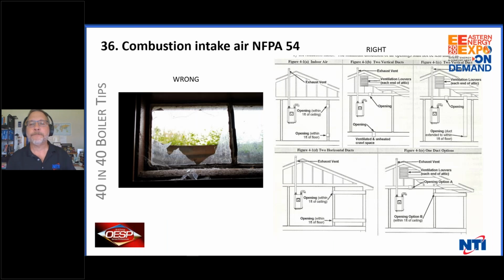Combustion air intake. From a friend of mine, Jim De Palma, who works for Weil-McLain, great guy, was nice enough to give me a visual on how much free air you need to use indoor air for combustion. He said if you have a 150,000 BTU boiler, you need 2 42-foot tractor trailers full of fresh air in the basement, open and free, no doors, no anything in between it.